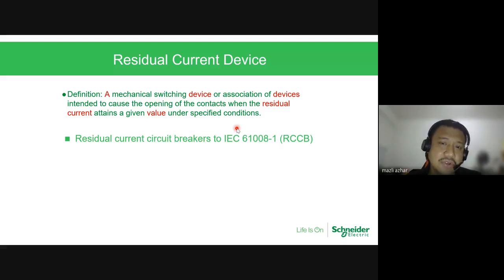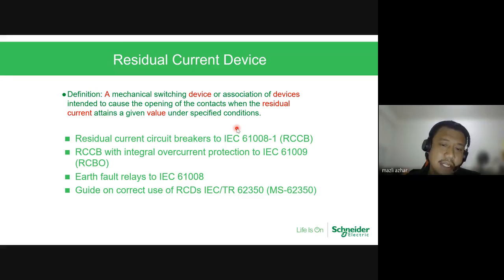All right, by definition, it's the same. So standard 61008 is for RCCB, 61009 for RCBO, Earth Fault Relay or ELR, and they have a guide to the use of RCD. These are all the standards that you need to refer to. And then MS IEC 61543, the EMC requirement. This last standard came into play in the past 2 or 3 years, whereby there was an issue when a guy brought a walkie-talkie into the panel room, power room, and when he used the walkie-talkie, the RCCB would trip due to the electromotive force. So this is where, under Suruhanjaya Tenaga, they require all RCCBs to comply with the EMC requirements to ensure that this nuisance tripping can be avoided, and to ensure the safety and continuity of protection being provided to the end user.